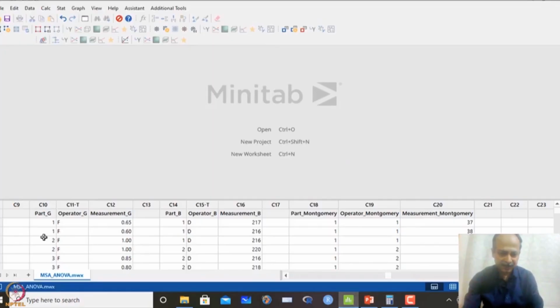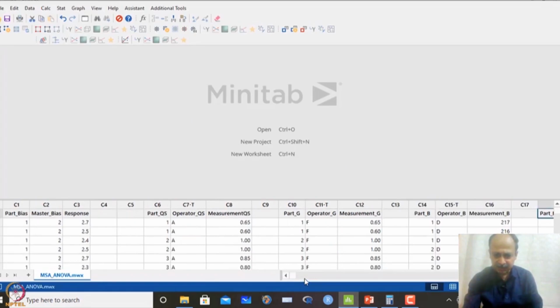The example that we have taken is one simple example, where one part measurement is given and the master specimen of that, the master's value of the master samples, is collected throughout the operating range. It can be from metallurgy labs or tool rooms. We have a masterpiece that we are measuring with this instrument.